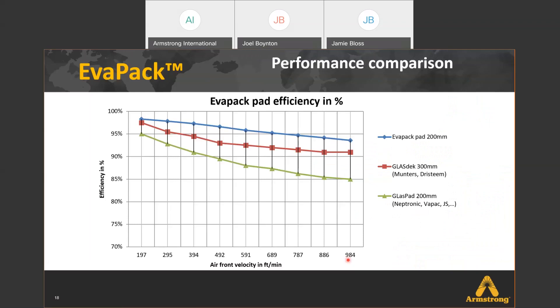Talking about pad efficiency with a performance comparison: on this efficiency chart, the y-axis shows efficiency in percentage and the x-axis shows velocities. Starting at a very low velocity, the efficiencies between GLASdek media, GLasPad media, and our EVAPAC media are pretty close. But as you increase velocity, the efficiencies drastically decrease in the two competitors. Also notable: while the competitors may hang in there a little, they are using a 300 millimeter pad compared to EVAPAC's 200 millimeter pad.